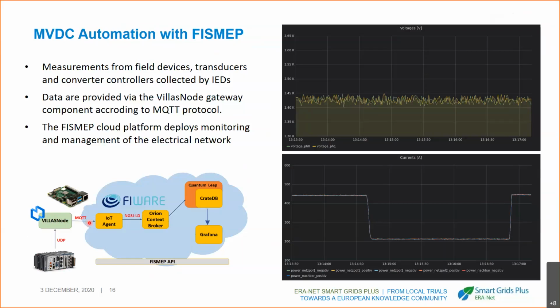Using the IoT agent, we can communicate with the Orion context broker, which is centrally managing all the streams of data that are coming, storing them in a time series database and visualizing them in Grafana. The monitoring of the distribution grid is carried out by setting thresholds that can raise awareness to the grid operator or initiate some corrective actions in the grid. For example, what you see here is the monitoring of the voltage and current in case of a change of a load that we have operated on the grid, with a decrease of current and consequently an increase of the voltage.